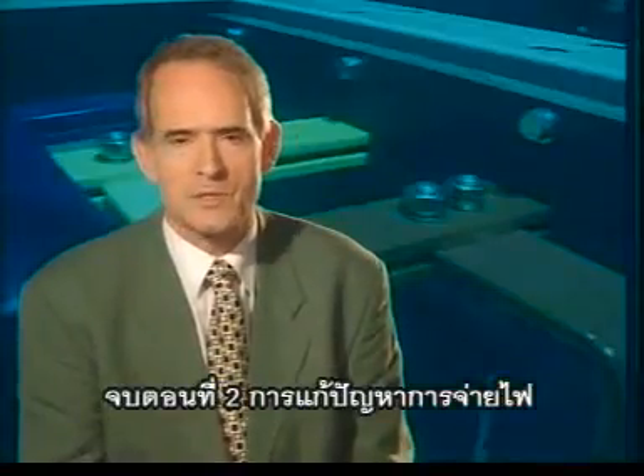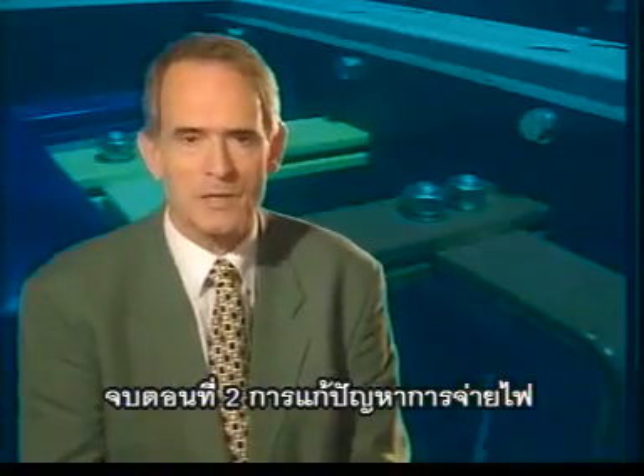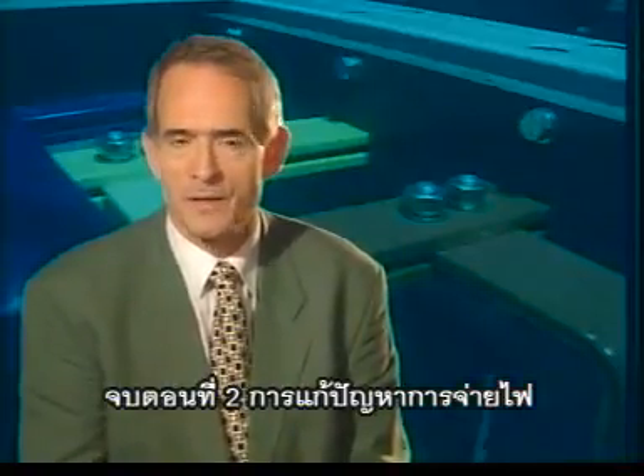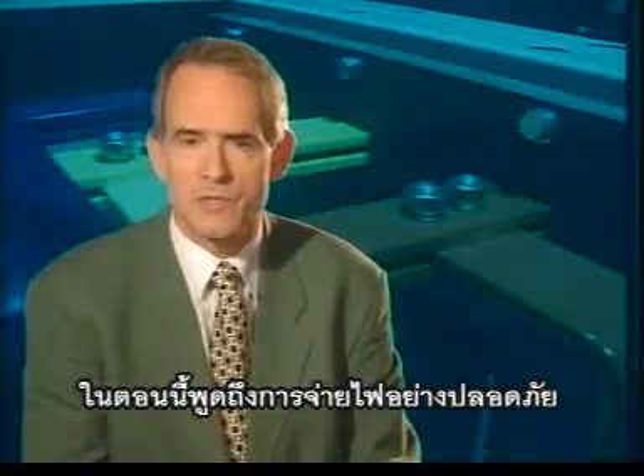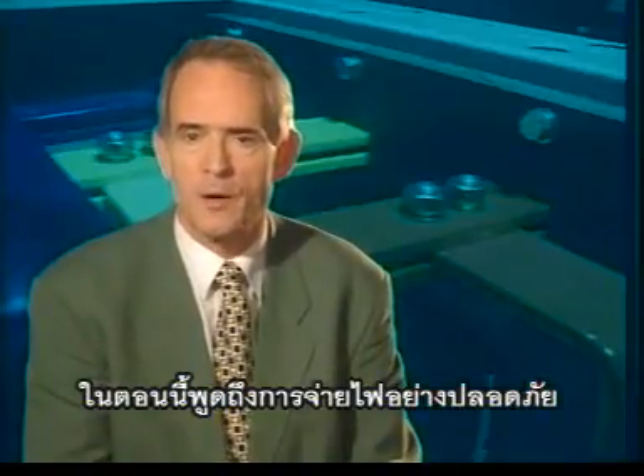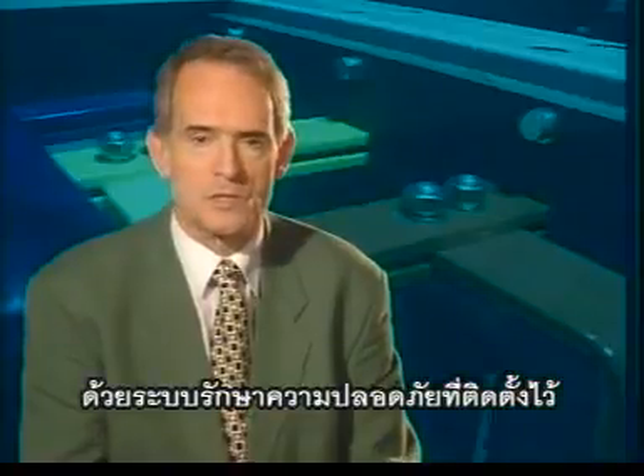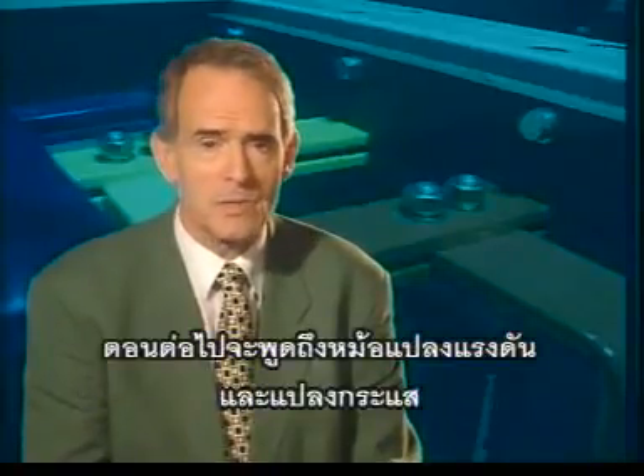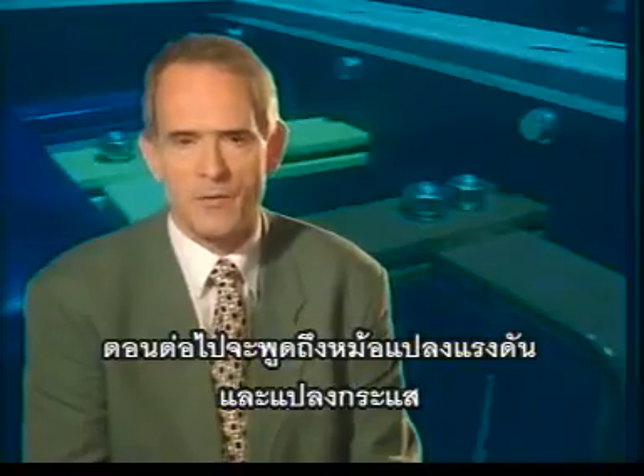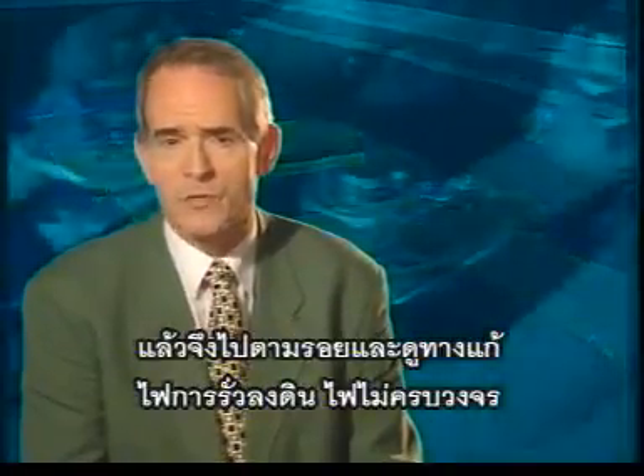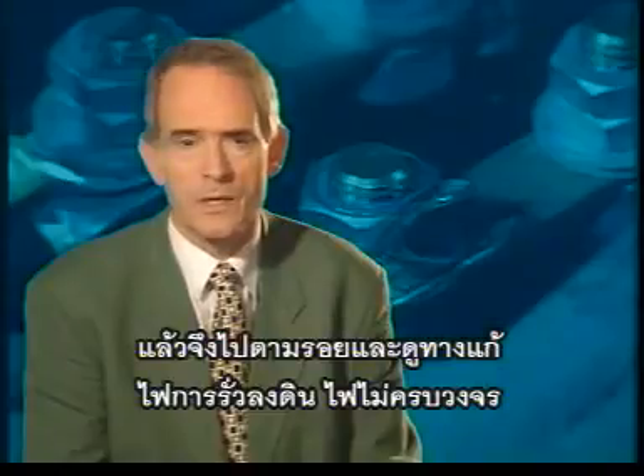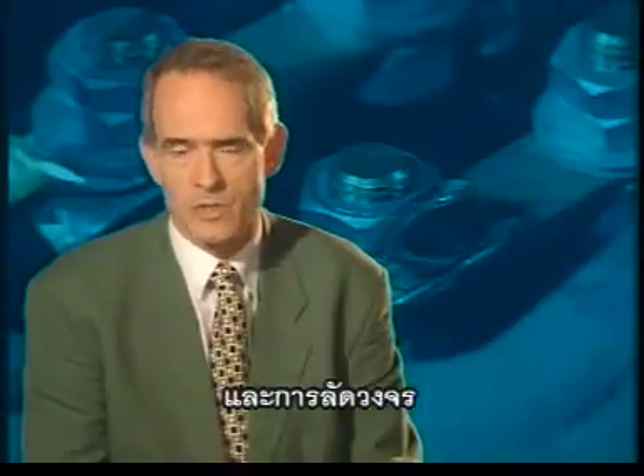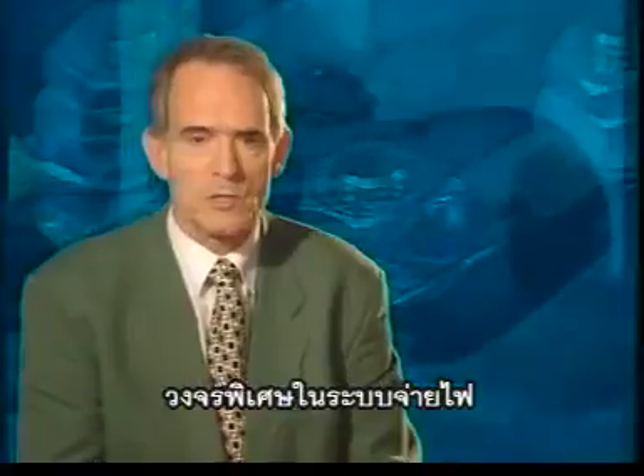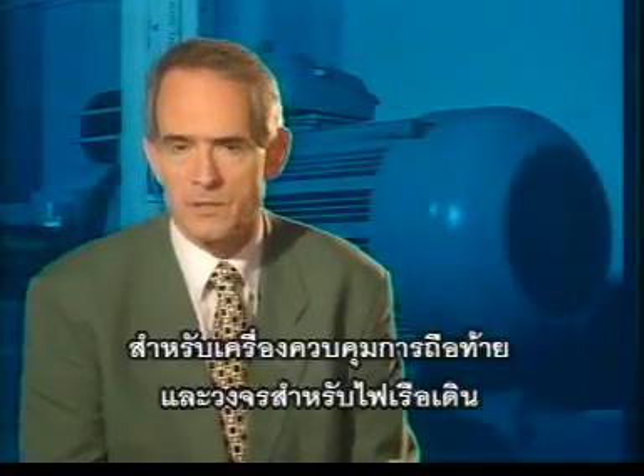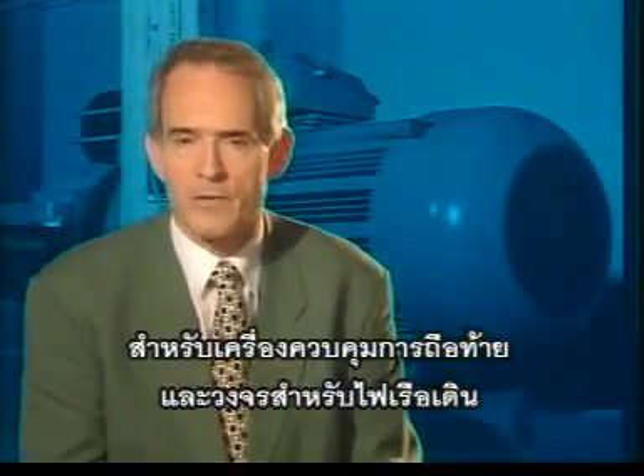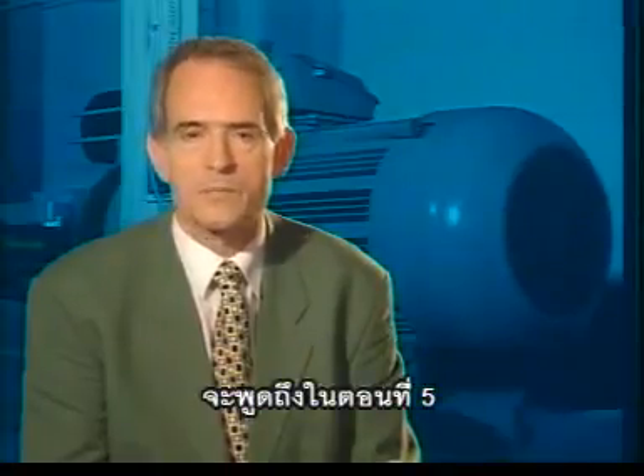This concludes the subject of Programme 2, dealing with the practical aspects of the distribution system. In this programme, we dealt with the method of safe distribution of the electrical supply on board ship, with all the safety systems built in. Next, we dealt with voltage transformers and current transformers. Then we traced and remedied an earth fault, an open circuit fault, and a short circuit fault. Special circuits within the distribution system, such as steering gear feed circuits and navigation lights feed circuits, are discussed in Programme 5.